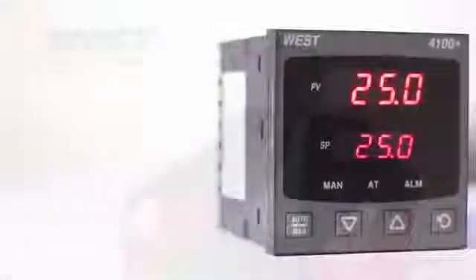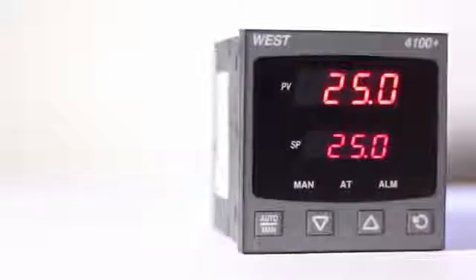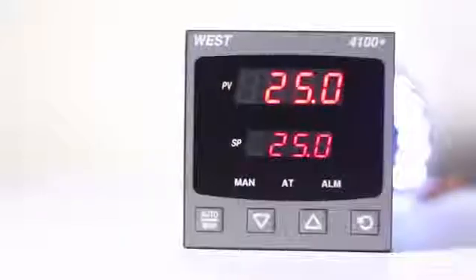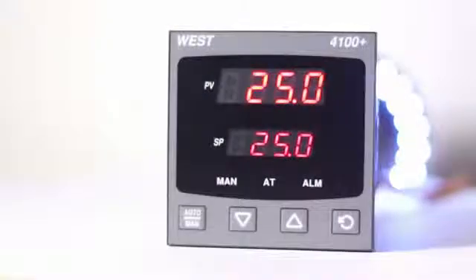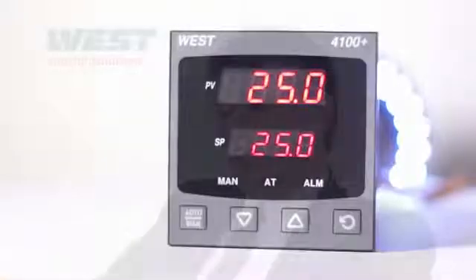As with many aspects of process control, compromise is needed. It's generally better to set the cycle time as long as you can get away with but still have adequate control in your process. The exception to this is if your process is entirely solid state in nature, in which case you can probably set the cycle time much lower.